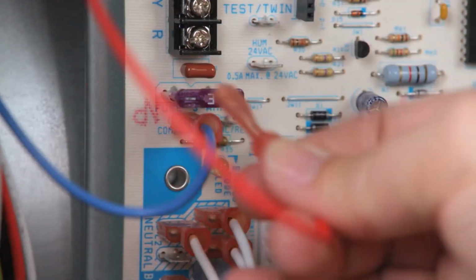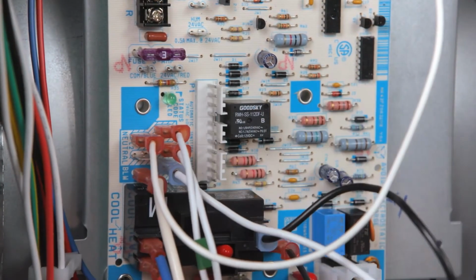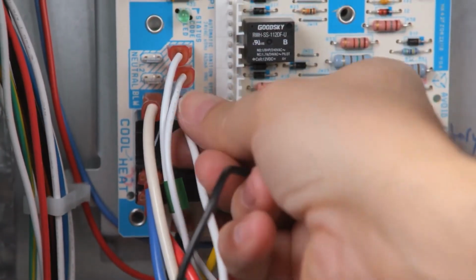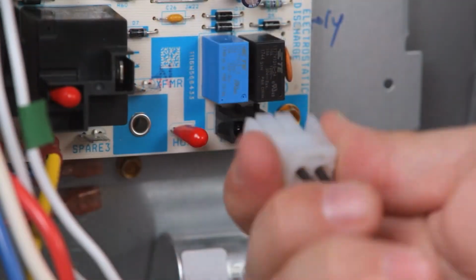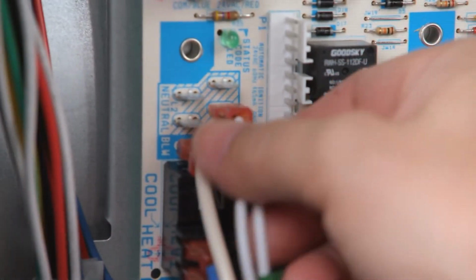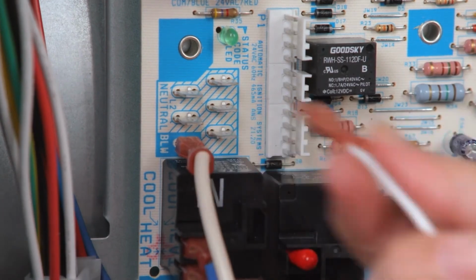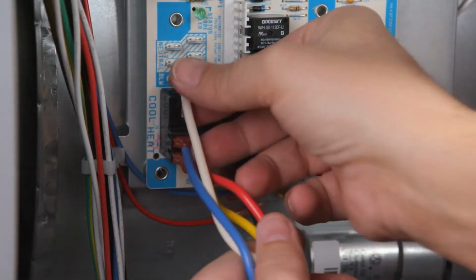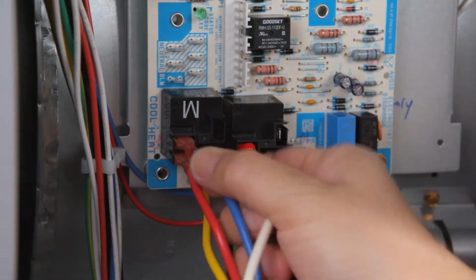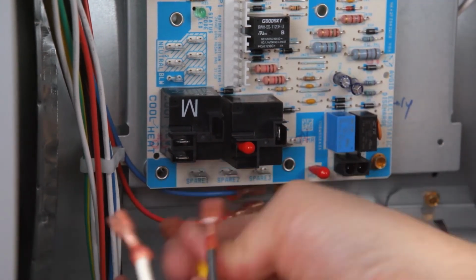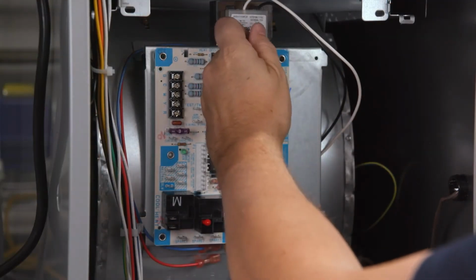Disconnect the thermostat wiring. Disconnect the 24-volt transformer wires. Remove the Carrier inline plug. Remove the 120-volt power and neutral transformer wires. Disconnect the 120-volt power and neutral wires. Disconnect the 2-pin Molex plug and neutral wires. Take note of what color wires are going to each terminal. Remove the blower motor wires for neutral, cool, heat, and spares. Finally, remove the board.